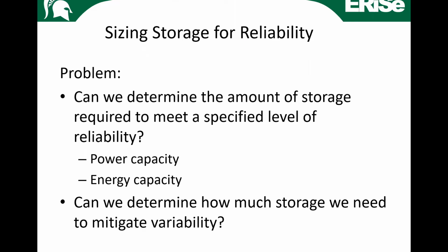Now with storage, because it's an energy limited unit, you have two elements to the capacity. Power capacity, that is how much megawatt capacity it has, how quickly it can deliver the power, at what rate it can deliver the energy, right? And energy capacity, just how much energy it can store and deliver. So we need both aspects of this.